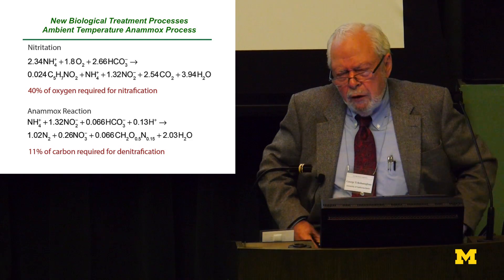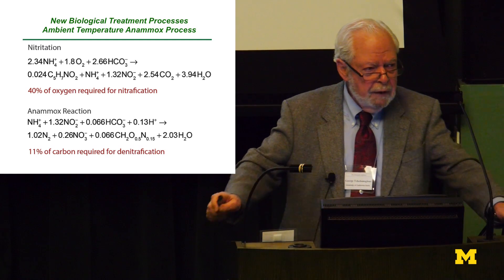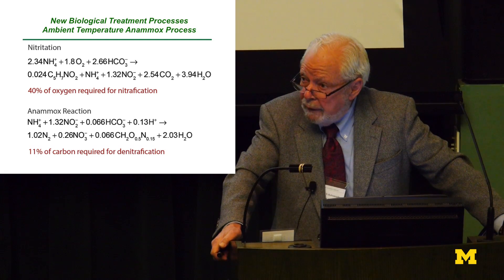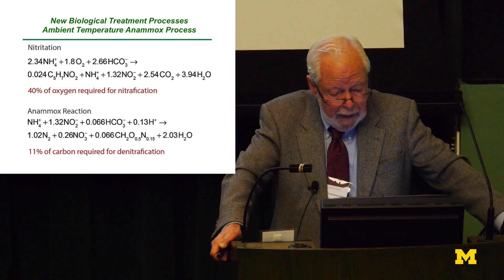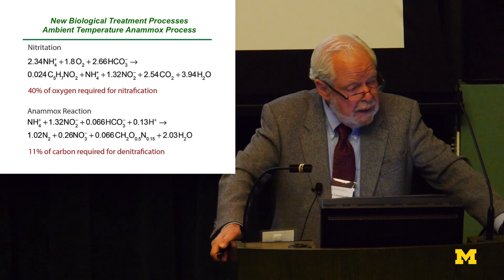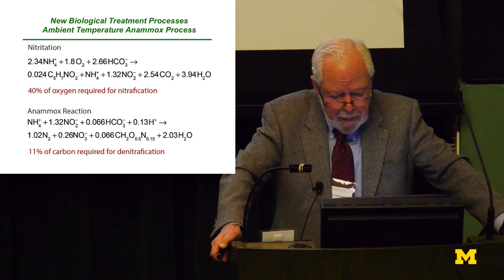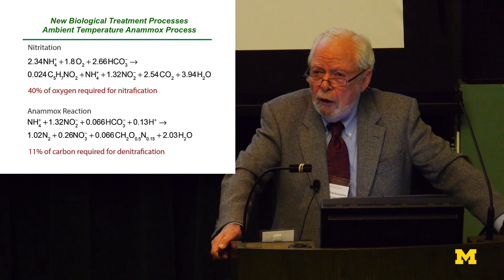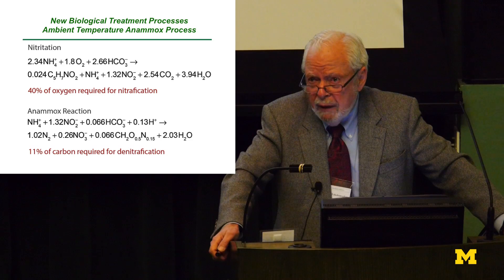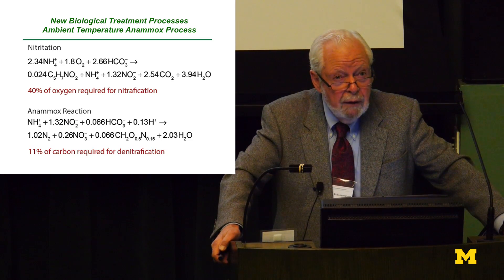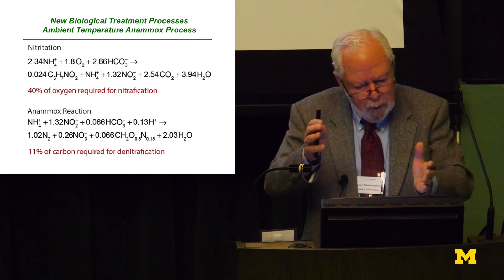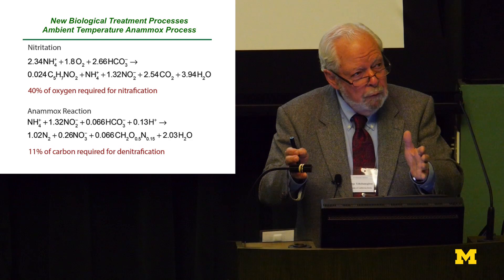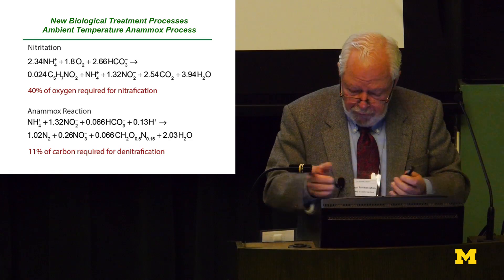There are exciting biological processes. The anammox process: instead of nitrification, you go to nitritation, and then the anammox reaction takes nitrite with ammonium and converts it to nitrogen gas. Advantages: 40% less oxygen use, 11% less carbon. It's been applied primarily to high-strength return flows, but researchers are working on ambient anammox treatment. I think within five years you will see this as a usable technology. The anammox bacteria were always there but weren't identified until about 12 to 15 years ago.